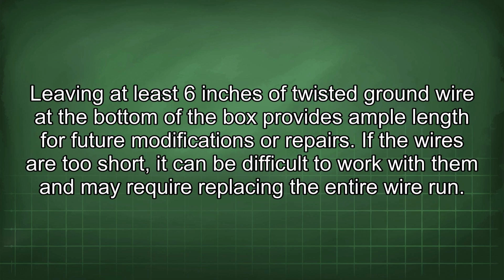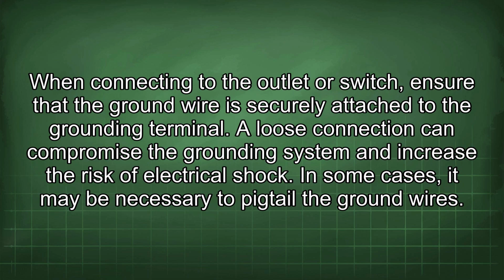Leaving at least 6 inches of twisted ground wire at the bottom of the box provides ample length for future modifications or repairs. If the wires are too short, it can be difficult to work with them and may require replacing the entire wire run. When connecting to the outlet or switch, ensure that the ground wire is securely attached to the grounding terminal. A loose connection can compromise the grounding system and increase the risk of electrical shock.